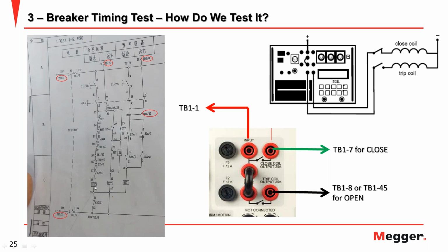The closing coil on the system, you need to find on the terminal block. If you put our connection, this one goes to the closing coil, TB17, and TB18 for the opening coil, and then positive to any positive point on the circuit. In this case, I just put it here on TB11 and TB12 for the negative point if needed. Like the Agile, we don't need to connect the negative point because we use it from the system. So we only need three connections to the control circuit. Again, only two connections: one to the main contact and the second one to the coil circuit.